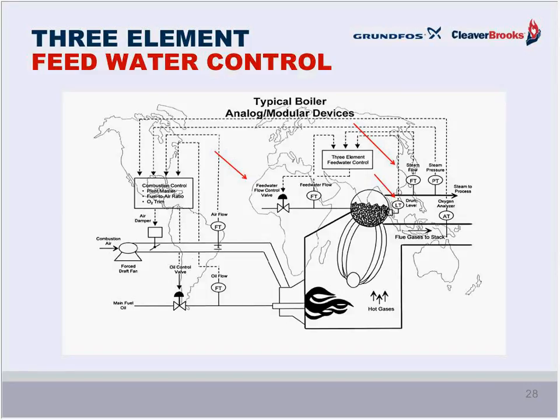And finally, you have the third element, the feed water sensing device. Again, probably a loop control working in conjunction with the level and steam element loops, and it's sensing a drop or increase in feed water supply pressure, but then intervenes in the adjustment of the feed water valve accordingly. In this case, the feed water control becomes the master, and the level and steam loops are subordinate to it. These systems, of course, have to be properly set up and adjusted in the field by a qualified technician based on the operating conditions within the plant. But once they're set up, they do control the feed water flow to the boiler very, very well.